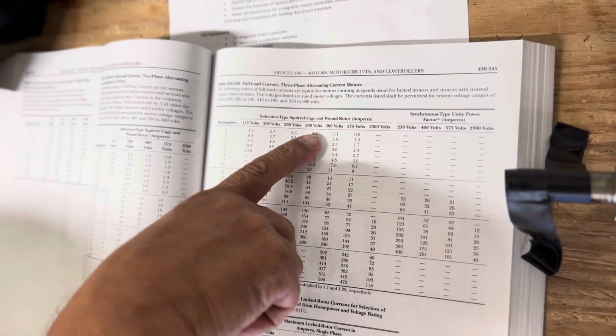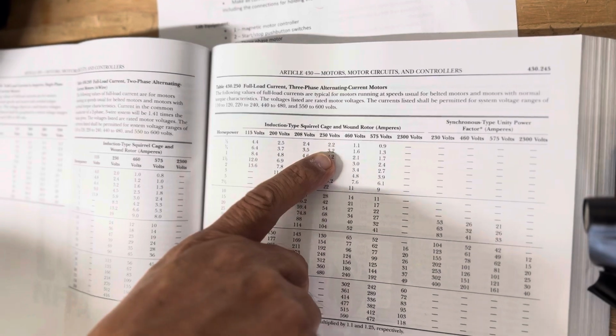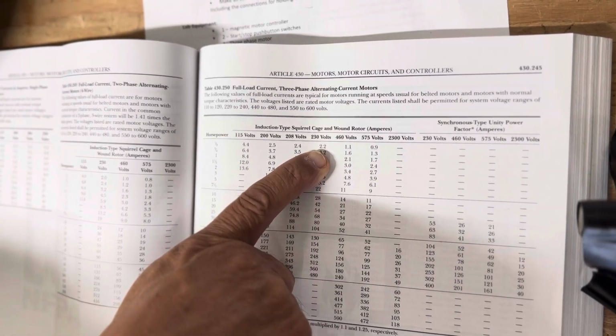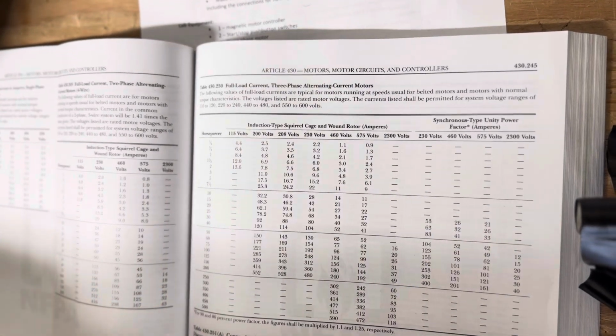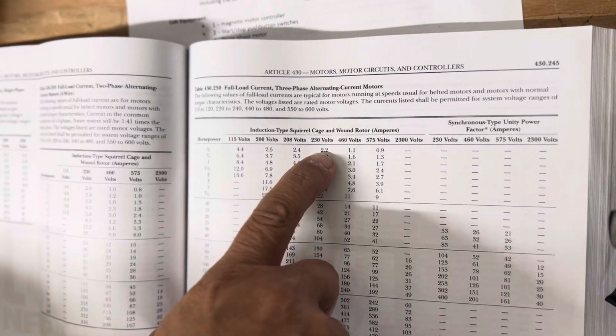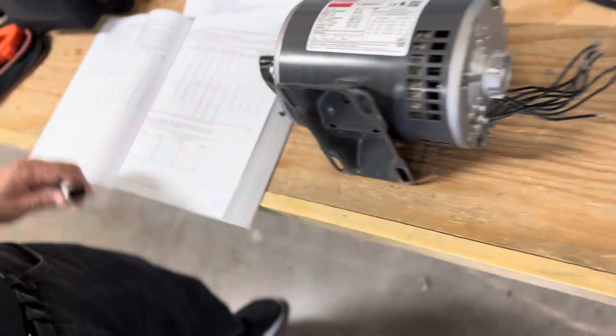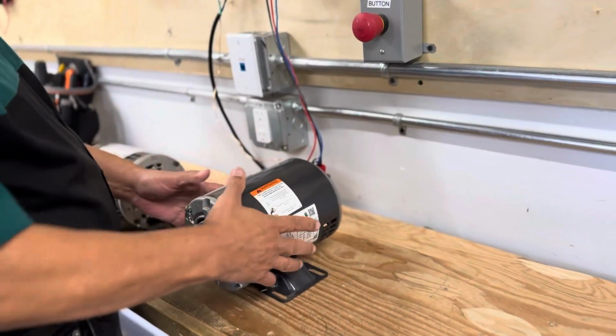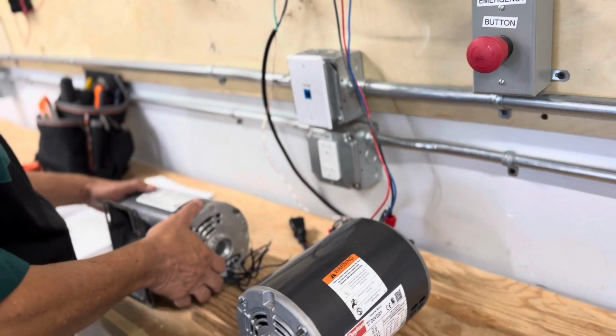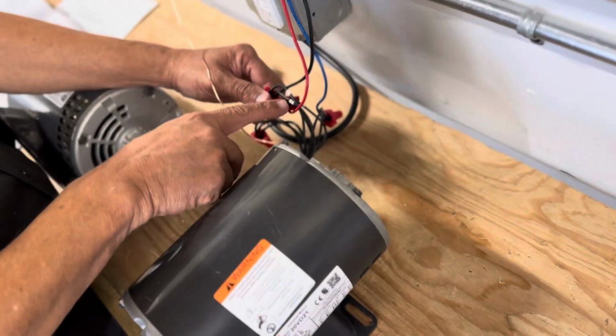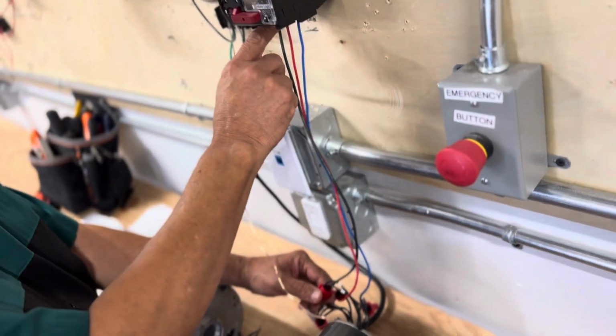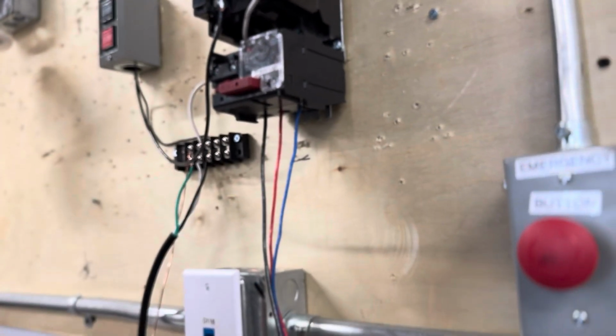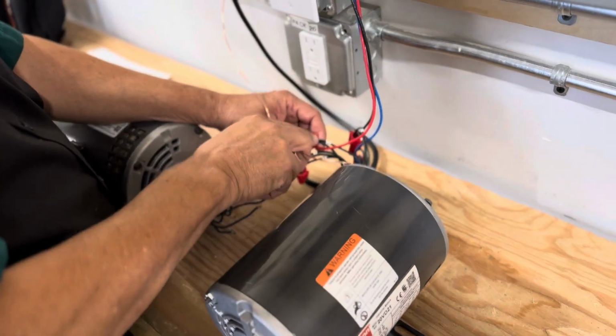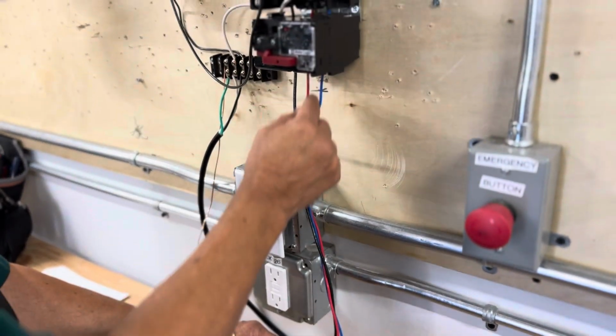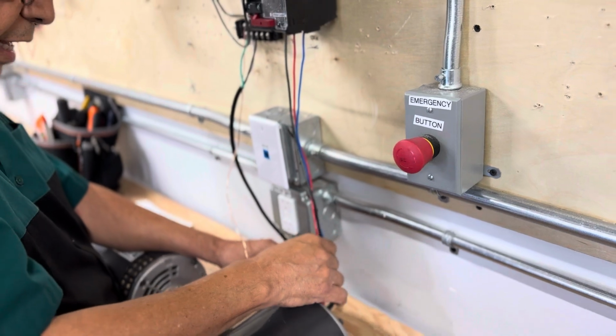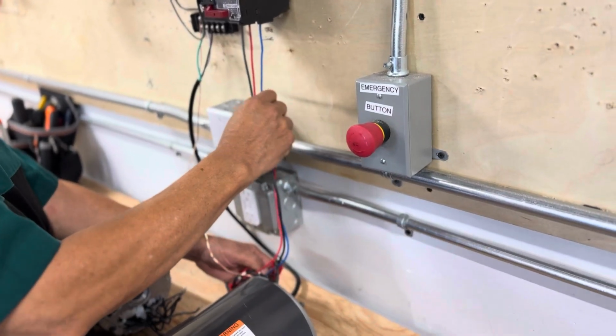With this, we can calculate, as we learned during the first lab, the protection using time delay, non-delay, dual element fuse, and or circuit breaker. So we are connecting this one. Let me go over this. As I told you, T1 and T7 are connected to L1. T2 and T8 are connected to phase 2. And T3 and T9 are connected to phase 3.